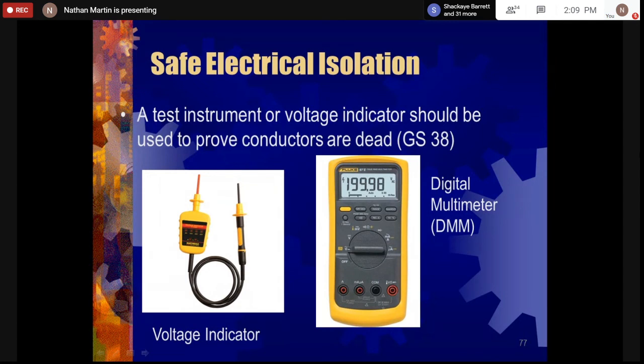If you look on your test lead for your instrument, for persons who have their personal multimeters, you will recognize you have a 10 amp fuse inside the test lead. However, because of how the test lead is designed, that fuse is a slow blow fuse, so it doesn't blow easily. However, when a test lead does blow the fuse, you're unable to change the fuse in a test lead because it's made as part of the lead.